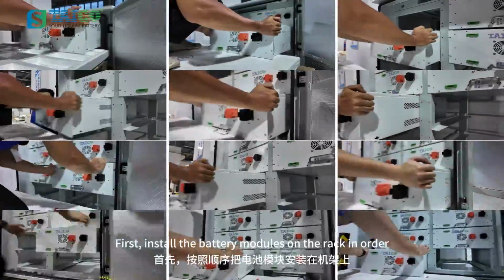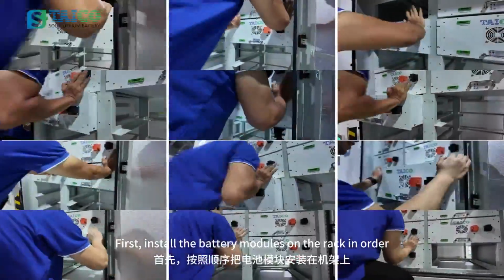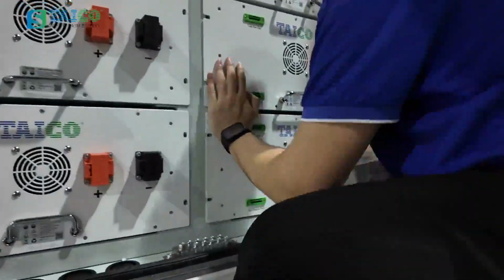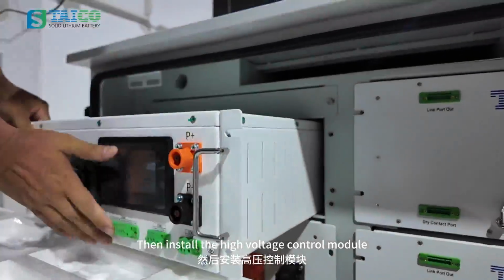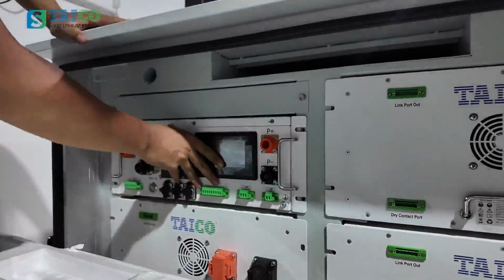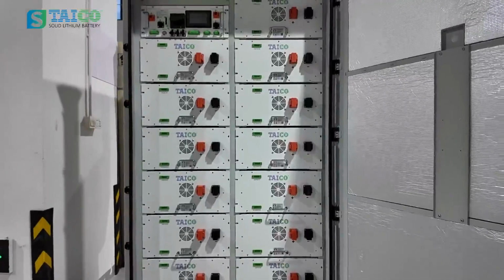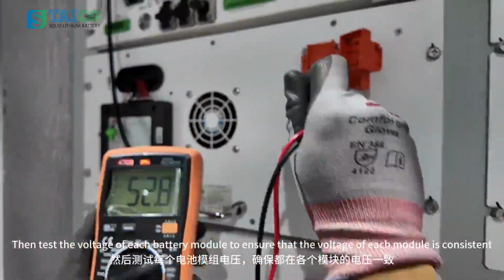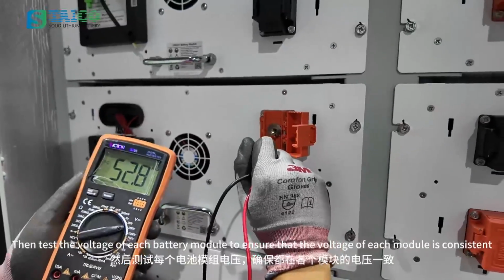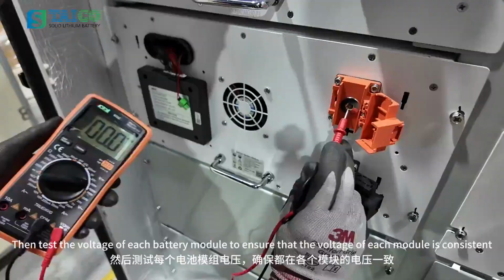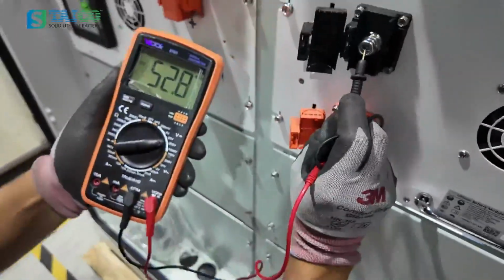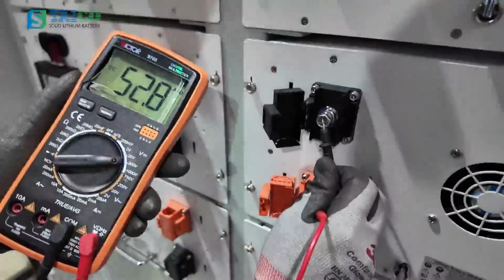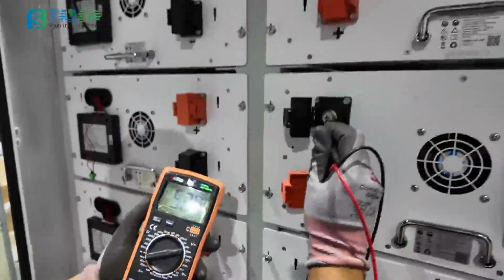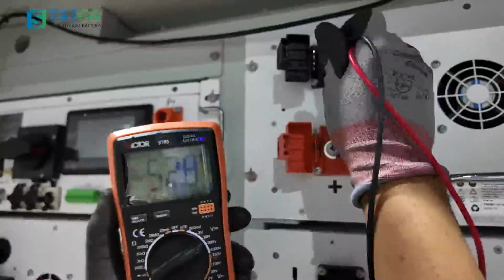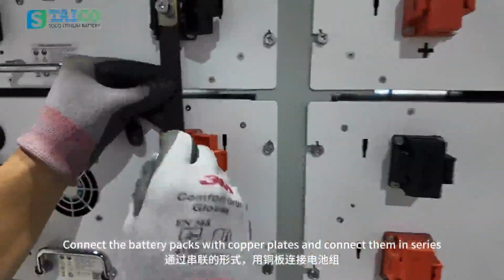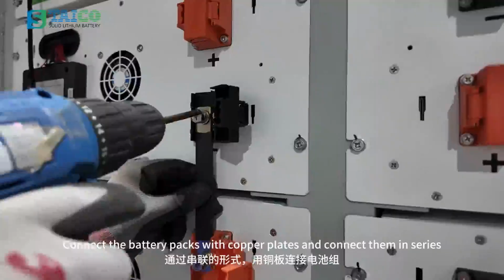First, install the battery modules on the rack in order. Then install the high voltage control module. Next, test the voltage of each battery module to ensure that the voltage of each module is consistent. Connect the battery packs with copper plates and connect them in series.